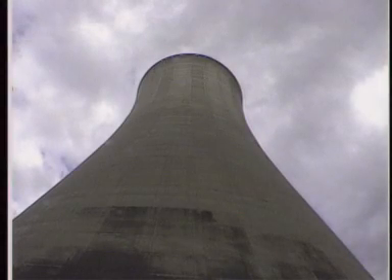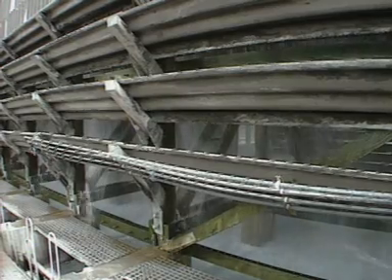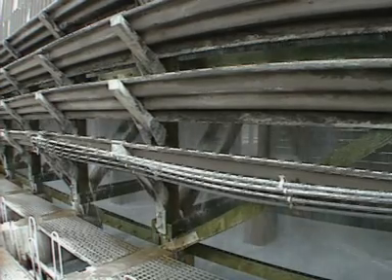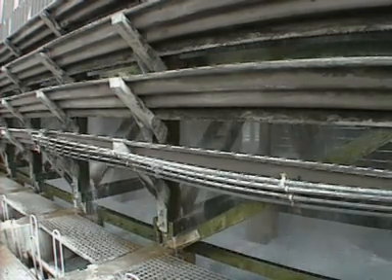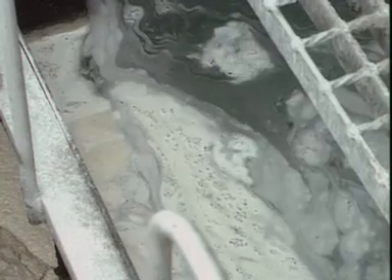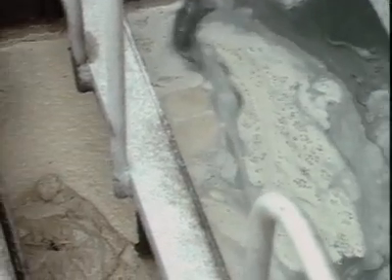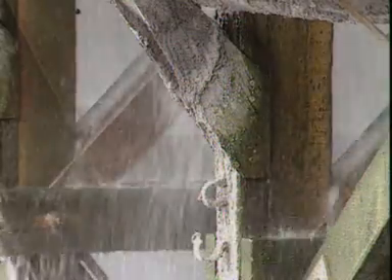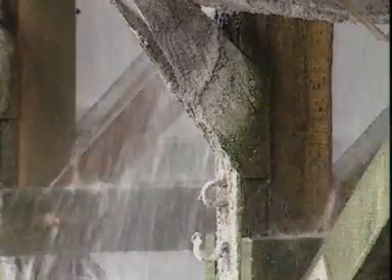Although there's a lot of spray in an induced draft cooling tower, there is little history of these towers causing Legionella disease. Cooling towers produce aerosols, and aerosols must be contained within the cooling tower, because the conditions there are ideal for Legionella to multiply. Water is at about 30 degrees Celsius. It collects dust from the incoming air. Leaves and other materials may settle in the pond, providing food for the bacteria. Rust and corrosion products may provide more food. A slimy layer called a biofilm may build up on the surface of the tower, sheltering these organisms. Because of this, regular cleaning and disinfection is necessary.